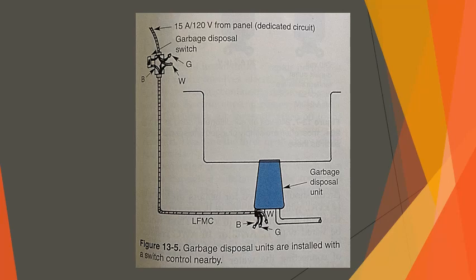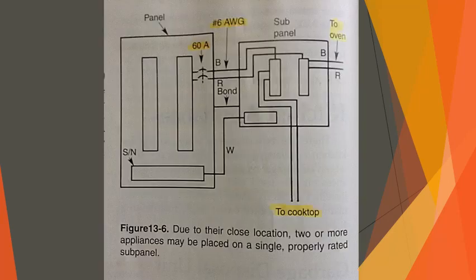Cooking tops and wall-mounted cooking units. Counter cooking tops and wall-mounted cooking units are each rated at approximately 7.5 kilowatts or 7.5 kVA and 120/240 volts. These types of units require special circuits and overcurrent protection in the form of fuses or breakers, usually 30 to 40 amps. They are connected in the same manner as ranges or dryers discussed earlier.